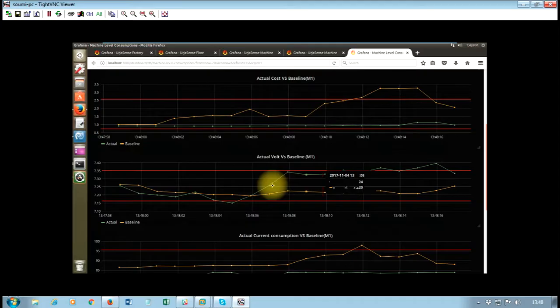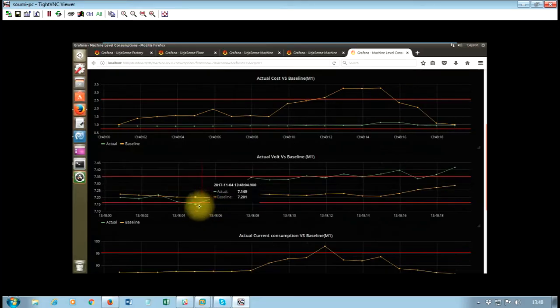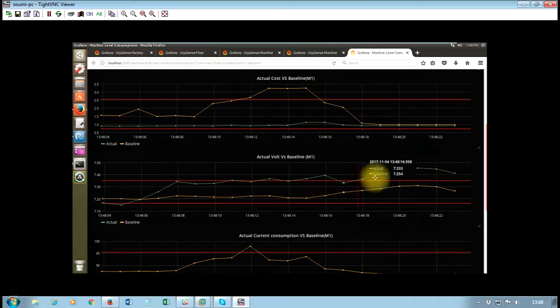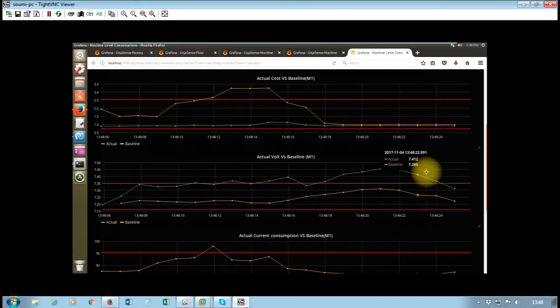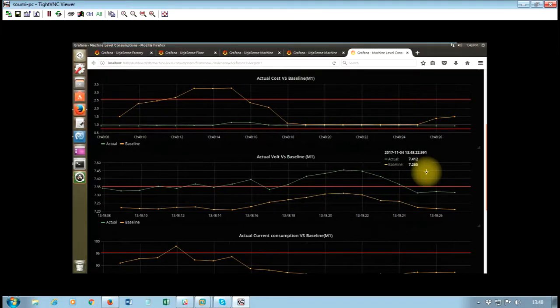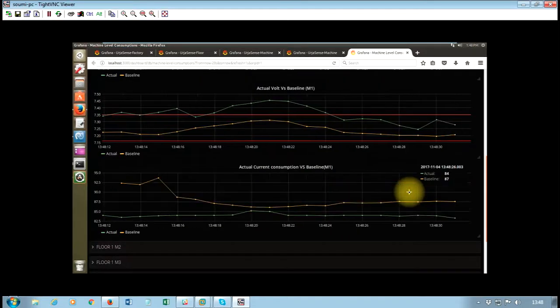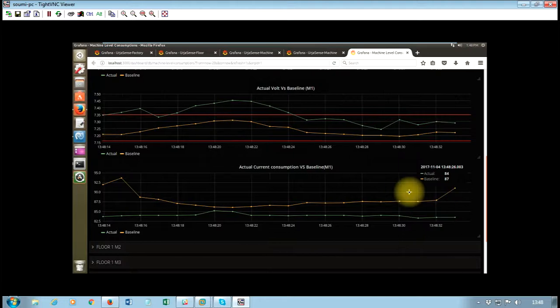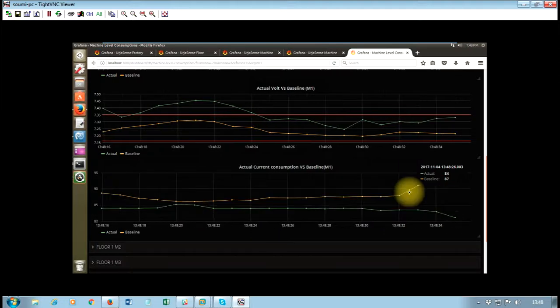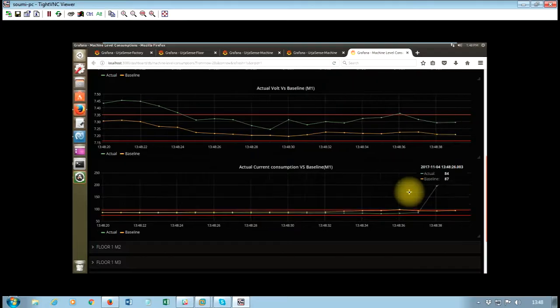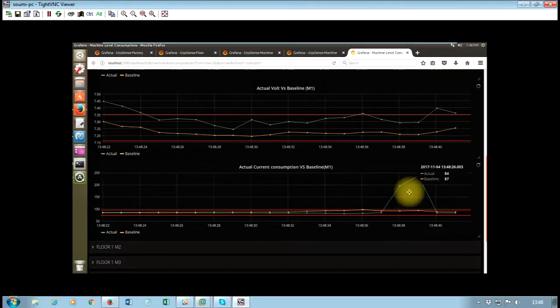And we can see that even the voltage levels were down, but it has now gone up and across the threshold on top. So the voltage is fluctuating at a very rapid rate. It's going from below the threshold to above the higher threshold, and this is unusual, and this is probably causing the disturbance that we saw at the factory level.